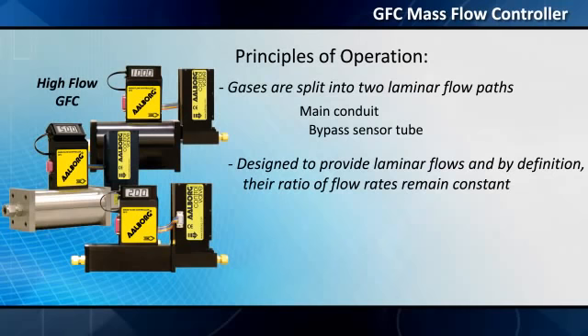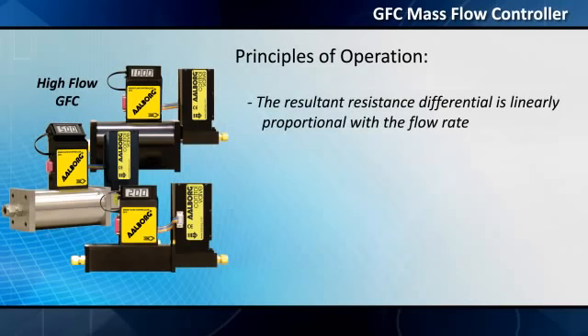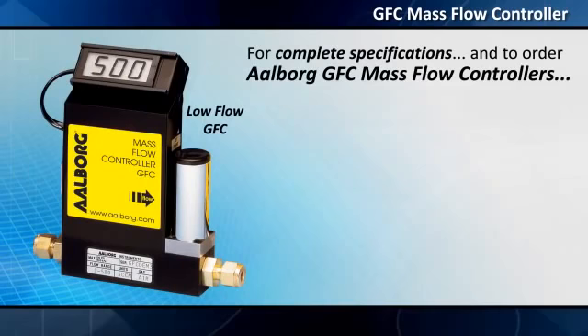Resistances of heated windings on the capillary sensor tube are monitored. As heat is carried from the upstream to the downstream winding, a temperature difference is created. The resultant resistance differential is linearly proportional with the flow rate. A built-in proportionating valve facilitates closed-loop flow control functions.